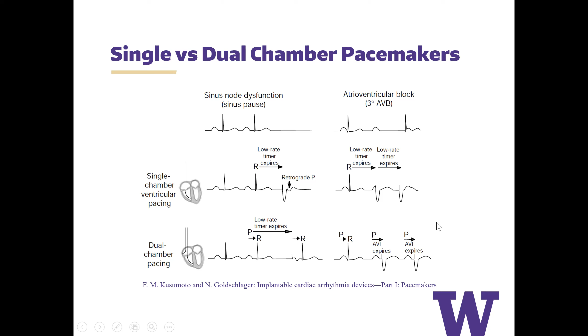In these patients, if they have a dual chamber pacemaker, what you will see is when you have a P wave here, it starts the AV delay. But here, because you have a sensed R wave, even though this was actually not conducted from this P wave, it is nonetheless a sensed ventricular impulse, and that actually inhibits ventricular pacing. And then the next P wave comes up, and here you can see that this arrow is longer than this because the AV interval here is longer. And so the AV interval actually expired, and you still didn't have an intrinsic QRS complex come in. So when that timer expires, the pacemaker will give a ventricular pacing impulse, and so on and so forth. So the benefit of a dual chamber pacemaker is obviously you maintain AV synchrony, whereas in single chamber pacemakers, you don't have that.